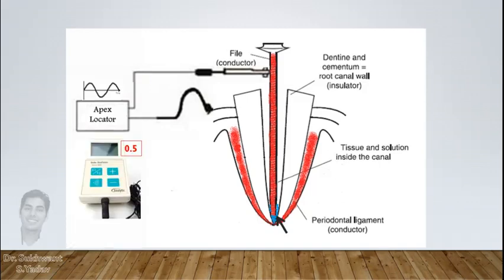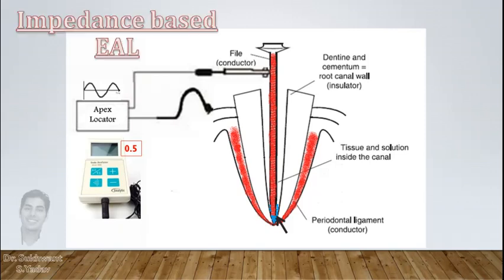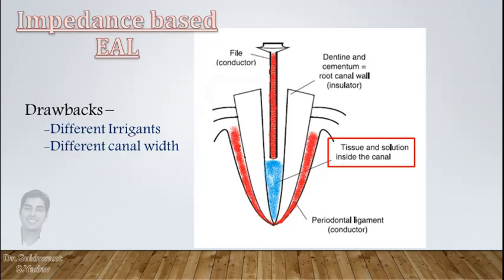Another finding was that there is sharp change in impedance at apical constriction which is recorded as 0.5 mark and considered best for working length determination. This is the principle of second generation apex locators. Main aim is to record apical constriction, but because the sharp change in impedance value differs in case of different irrigants or different canal widths, it cannot be recorded accurately.